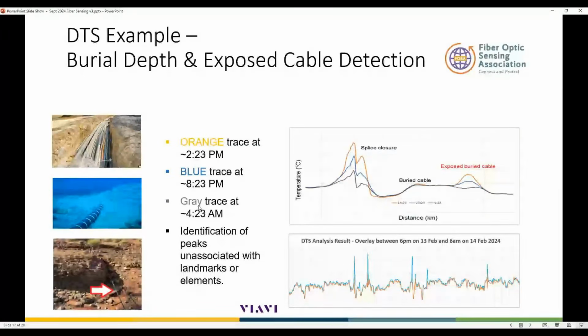The blue is at 8:23 in the evening, and the orange at 2:23 in the afternoon, during the hottest part of the day. The temperatures are fairly similar throughout the buried length of the cable, but where it's exposed, we see variation from cool early morning after being in the dark all night, to the hottest in the afternoon, with the evening in between.